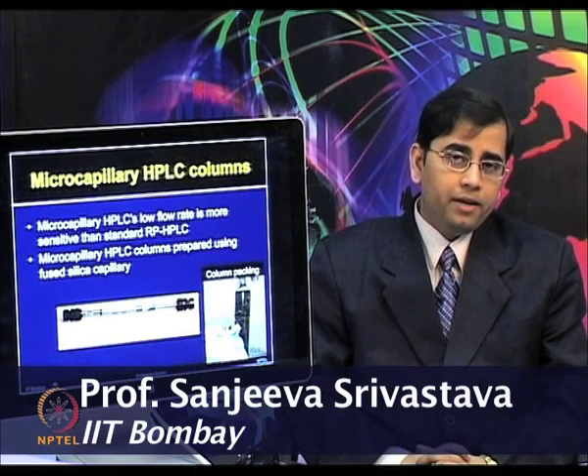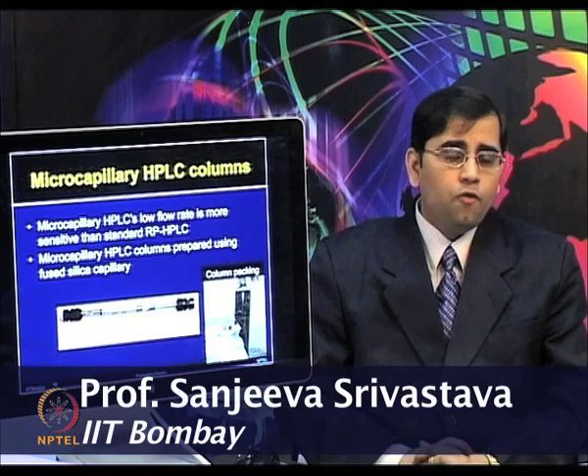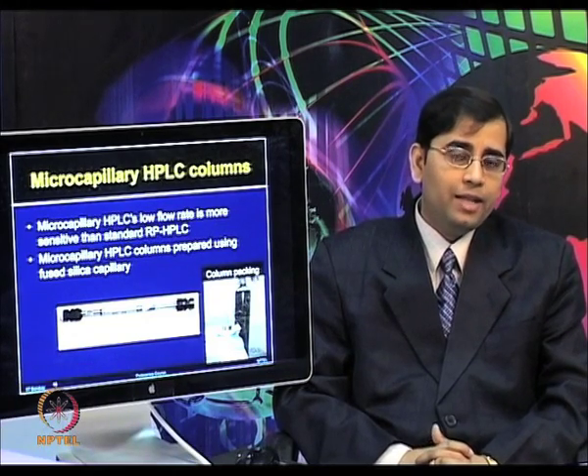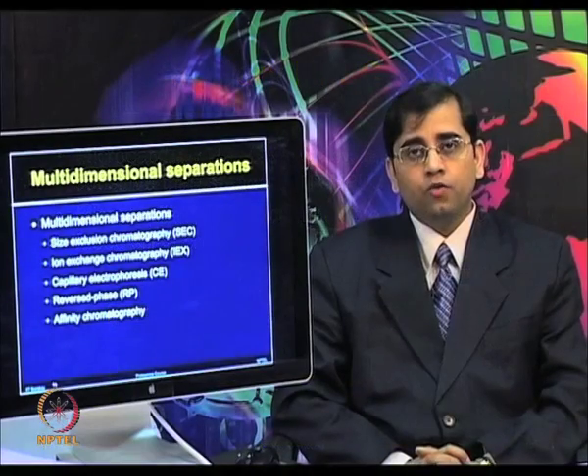HPLC can be micro capillary, nano LC, or different types of chip-based chromatography separation. For proteomics, various types of micro capillary, nano LC, and different chip technologies are currently used. In micro capillary HPLC, the low flow rate — which is less than 1 microliter per minute — is more sensitive compared to standard reverse phase HPLC at around 50 microliters per minute. Micro capillary HPLC is required for analysis of low femtomole amounts of peptides. One can prepare micro capillary HPLCs by using fused silica capillaries packed with reverse phase packing material.